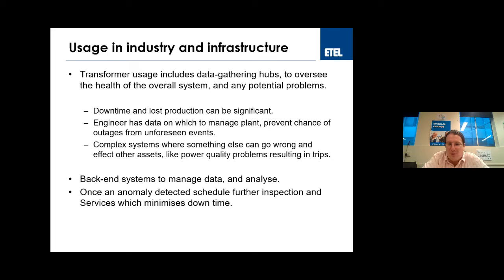If we put online monitoring on the transformer, we're not only looking at the health of that transformer, but also everything around it, because something else happening on the system might start to stress other components. So the transformer itself can start to put its hand up and warn us of potential problems it's seeing around the system.